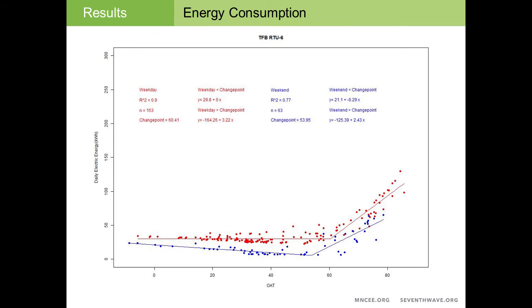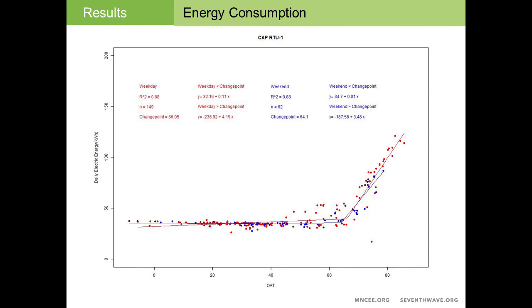So shifting to the electrical graphs, we look at the change point models for the electric graphs, and here is another example of a very clean model that shows a good relation between outdoor air temperature and weekday, weekend periods, where you don't have any cooling that activates until a change point of about 60 degrees for this particular unit, and then a relatively flat consumption below 60 degrees, which is attributed to the fan energy. Another site has no indication of weekday, weekend change. This has energy use that's pretty predictable. It did have a programmable thermostat, but it was not changing the values sufficiently enough to show a difference.